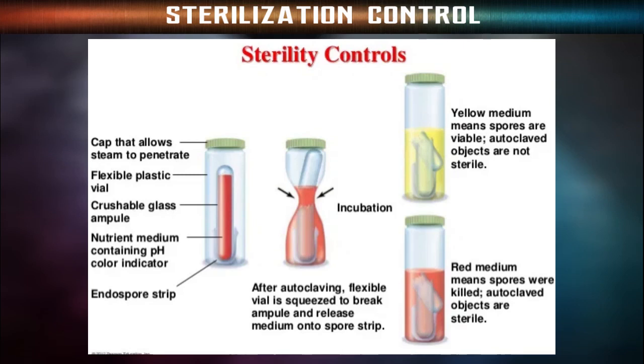And if the center is sufficiently heated, then it means the desired temperature is achieved. Autoclave tapes are not fully reliable because they do not indicate how long appropriate conditions were maintained. Next is thermocouple or Browne's tube. A thermocouple is a temperature measuring device that records the temperature by a potentiometer.